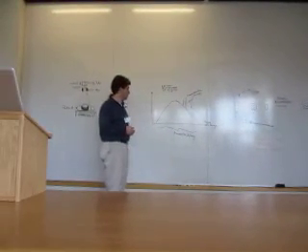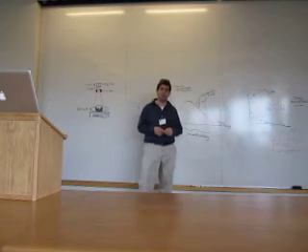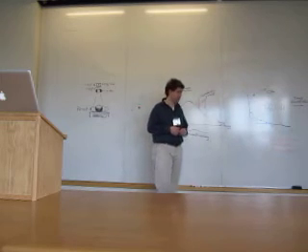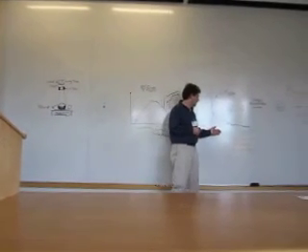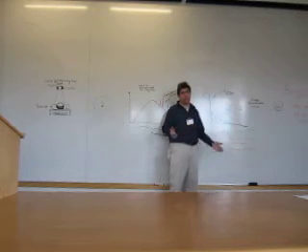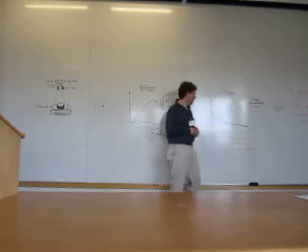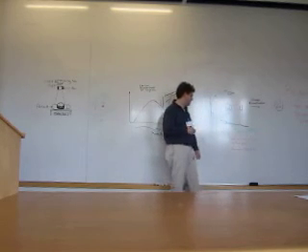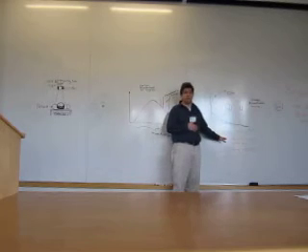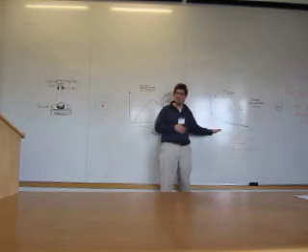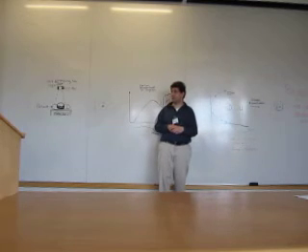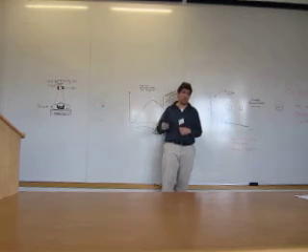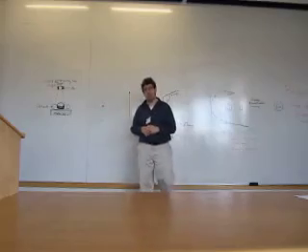This whole process is aimed at trying to get information about what those X-rays are doing as they go through the body, which is being absorbed. And how often those X-rays are absorbed depends on the density of the material, and also depends on the energy of the photon. In any case, the general formulation is this exponential that you integrate through the body, and you also have to integrate over not just distance, but also energy, since this is a multi-energy spectrum. So there are lots of corrections to this equation, and it's not justice for me to just write this one little equation up and say this is all we do, because there are a lot of things that go into building a patient imaging system, a lot of corrections that I'm not going to have time to discuss today.